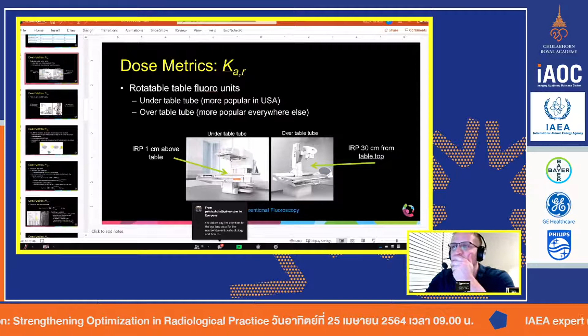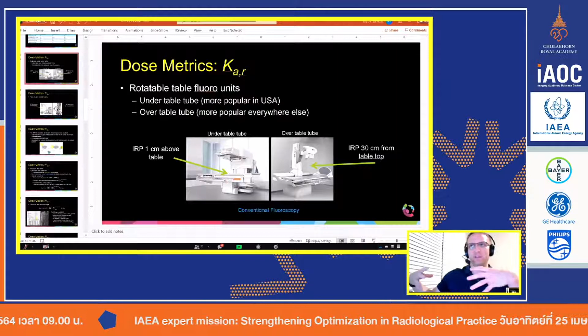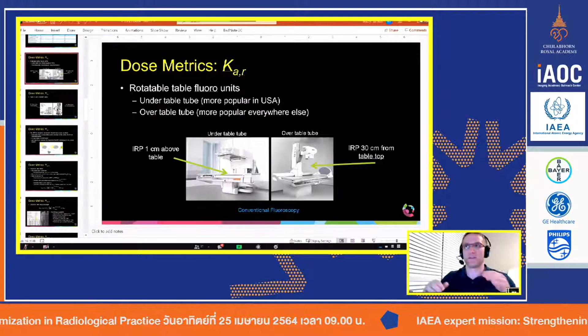So the first one is, should we do the report when we found the CAK higher than 5,000 milligrays? I would say yes. At my institution, that's my threshold. So if the cumulative air kerma is 5,000, then I, the physicist, will do the dose calculation. Now, we had a patient just a couple of months ago. It was a cath procedure. So they had biplane. One was over 5,000, one was 4,500. And we did the calculation for both. And you would expect at 5,000 and 4,500, you would expect to have some kind of tissue effect, some reddening, maybe some hair loss. Nothing. So we talk about that dose rate effect helping save our skin from having all of these effects. I still will do my calculations at 5,000 just because I want to be safe.